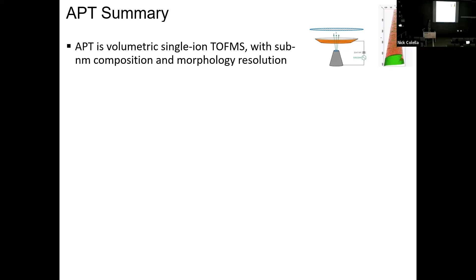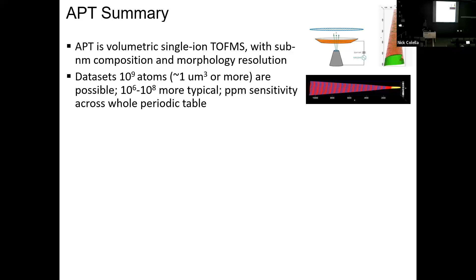Caveat, hydrogen. Yes, we can detect hydrogen. The trouble is our atom probe is made of steel, and steel is actually porous to hydrogen. Hydrogen just runs right through steel like it wasn't there, slowly, but it does. So there's always some hydrogen background, which means our detection sensitivity for hydrogen is more like parts per 100,000 or worse. Not great. There are ways around that. If you think you've got hydrogen in your sample, you want to see it, just fill your sample full of deuterium, because there's not a lot of that out in the world. And again, we can tell the difference. So no problem. You can buy deuterium. If you can fill your sample with tritium, that's even better, but don't bring it to me.